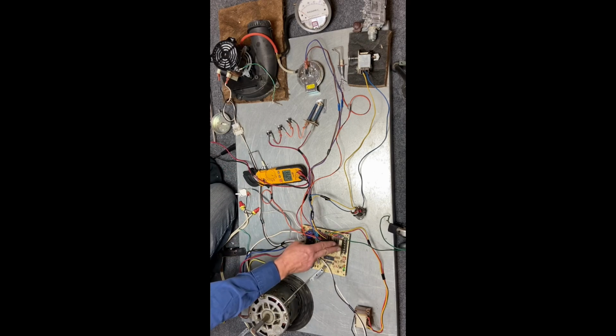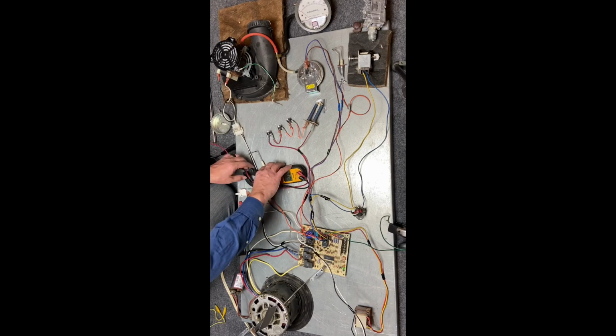If you notice, I disconnected the call for cooling, but the fan motor is still on. These control boards have a time delay built into them where they'll keep the fan on to get that extra cooling, so to speak, out of the evaporator coil. We're moving air across that evaporator coil. The refrigerant's still flowing as it's equalizing, so the idea is it makes it more efficient. We hear the click of the relay, and this fan motor shuts off. So all of these wires, once you break them down specifically, what am I looking for? What does this component do? It's very simple to diagnose it.